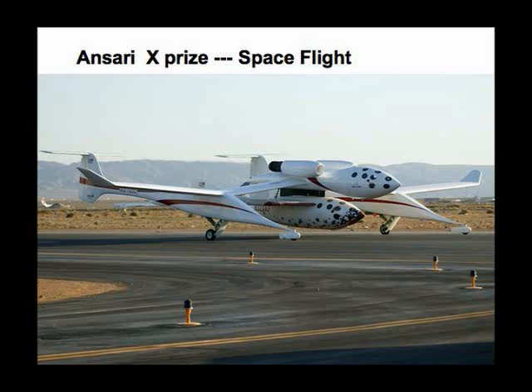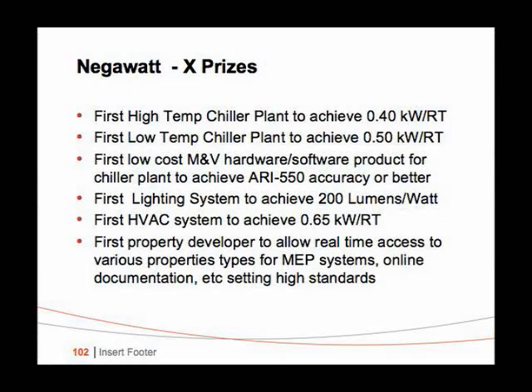You've all heard of the Ansari X Prize, right? This is rocket science. And for the Negawatt, I would call them the Negawatt X Prizes. The first high temperature chiller plant, in other words, run at 12 degrees, 13 degrees, 15 degrees, system at 0.4. The low temperature plant at 0.5. We're already doing 0.58, so this is not a big stretch.